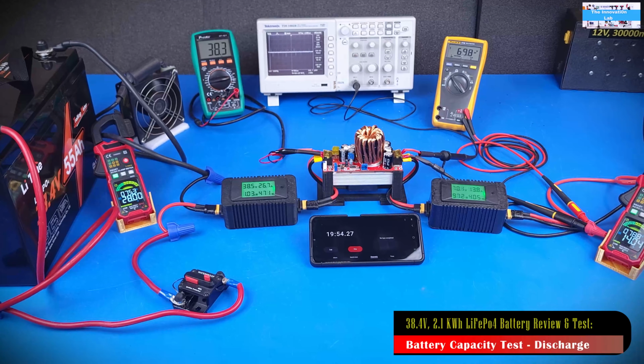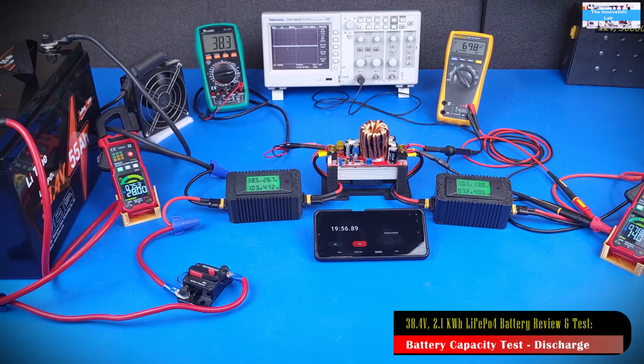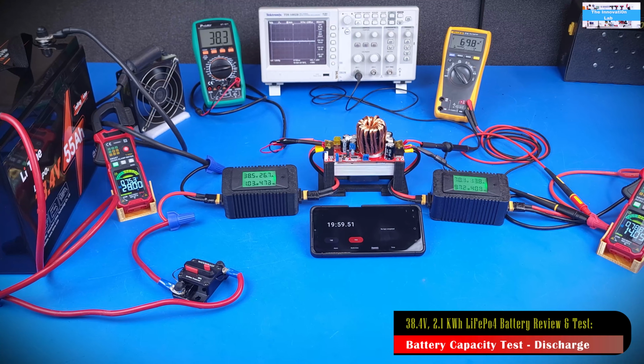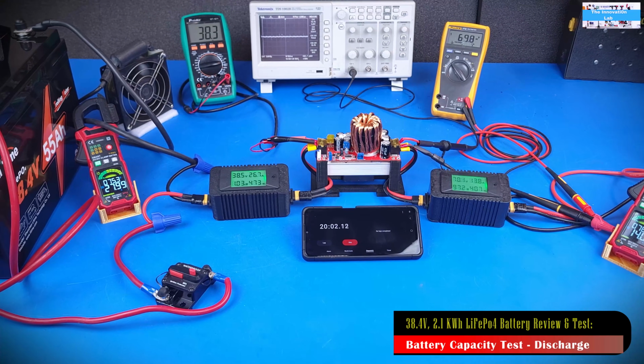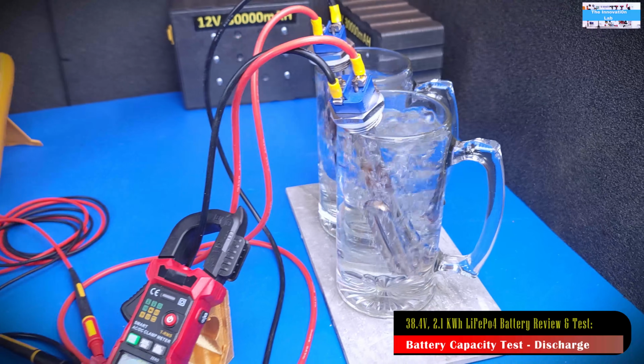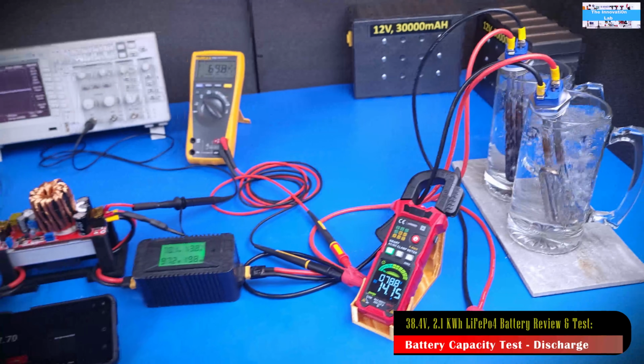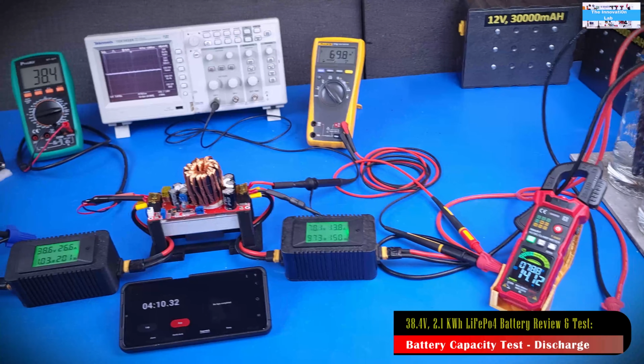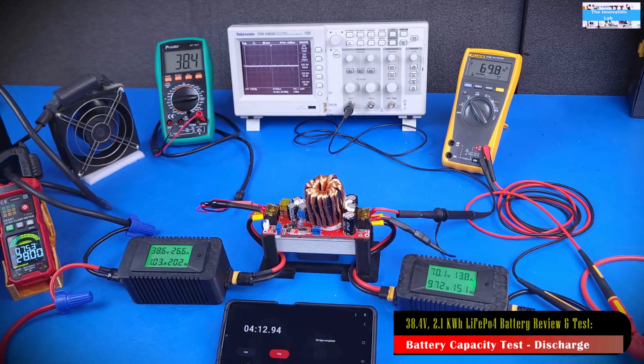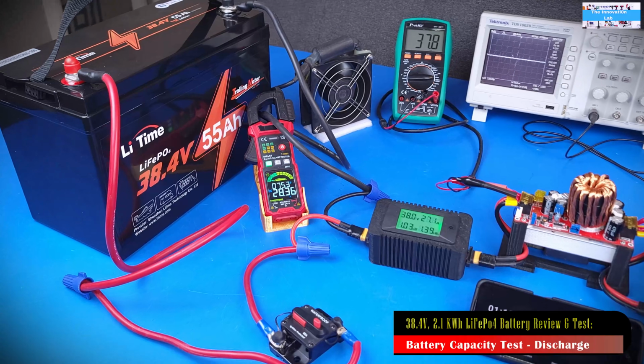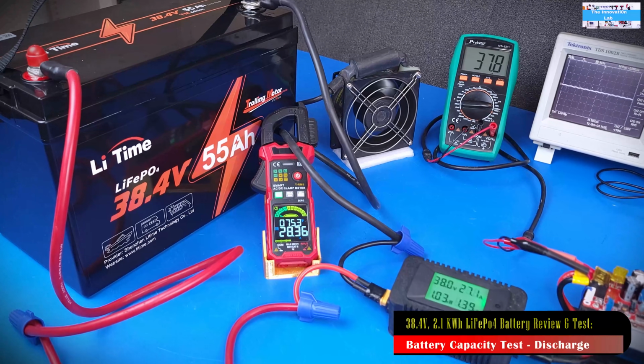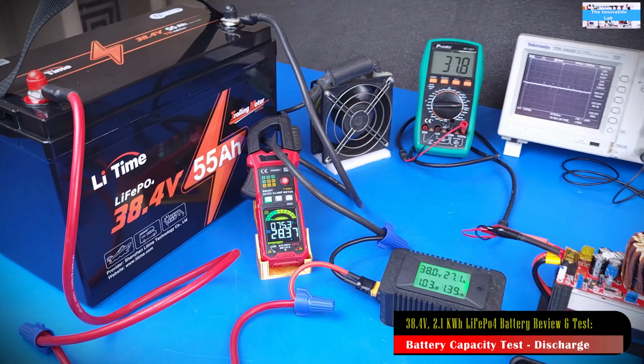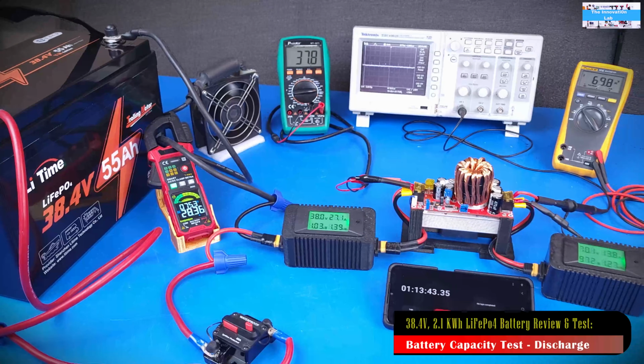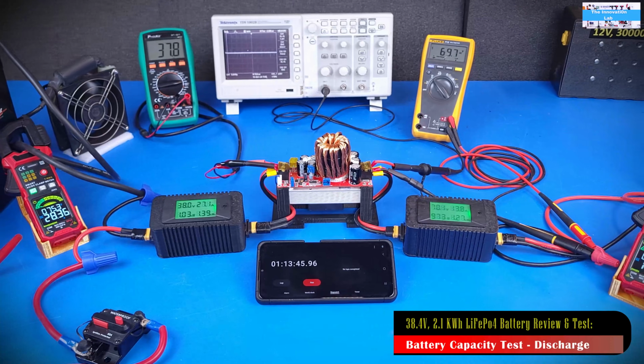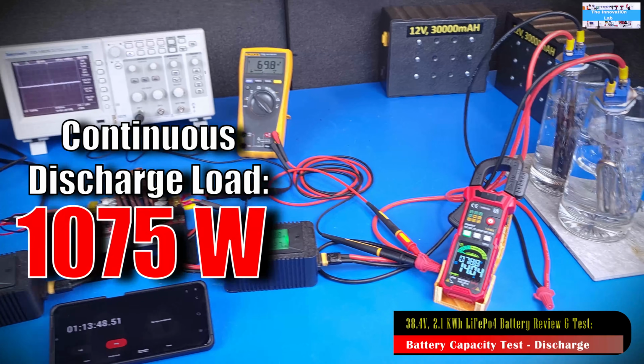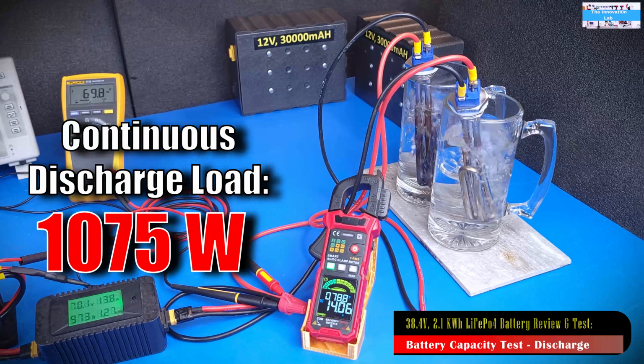To get close to our discharge goal of about 1000 watts, we had the output of the DC to DC boost converter set to about 69.8 volts, delivering a load current of about 14.14 amps. But a realistic power draw from the battery system, accounting for all the power losses and boost converter efficiency, really comes from the back end, the actual battery voltage multiplied by the supplied battery current. When you do the math, we are actually discharging the battery at the rate of about 1075 watts, which is quite impressive.